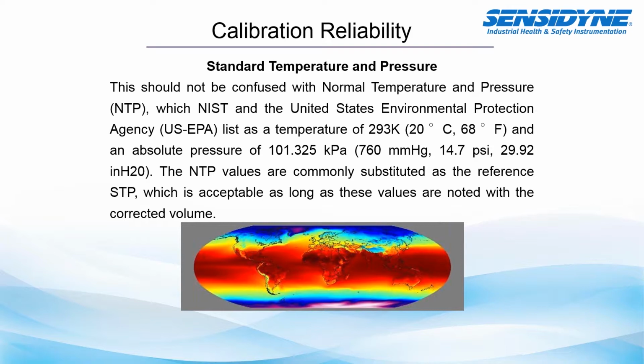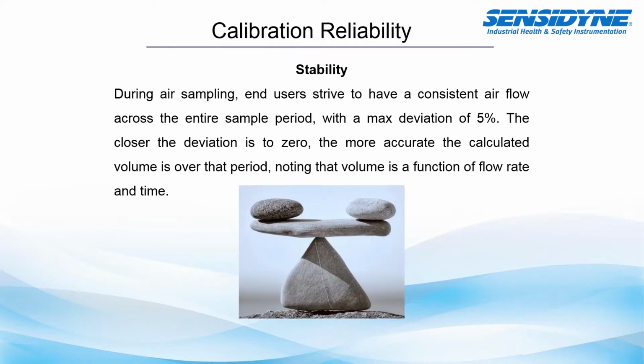The key takeaway here is whatever you're using to standardize your volume in your pre-calibration, you should use and cite that same standard when you are converting your post-calibration volume and/or flow rates.